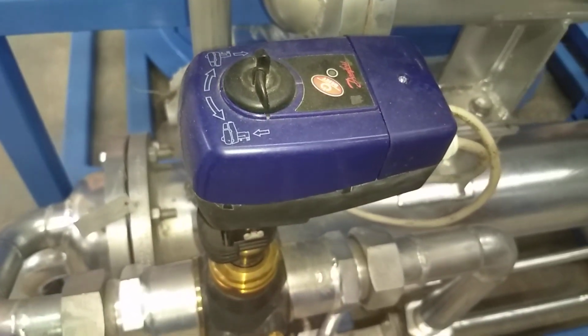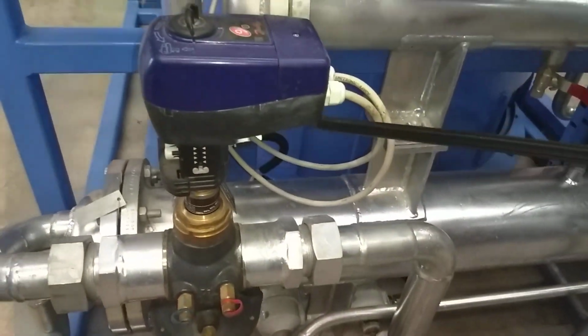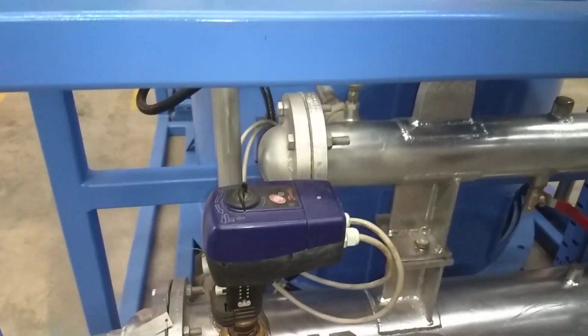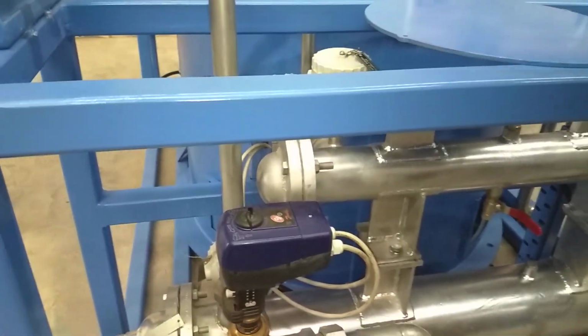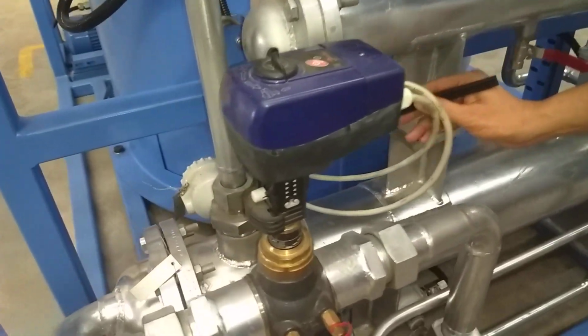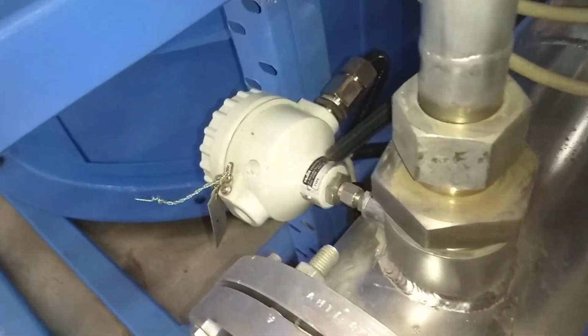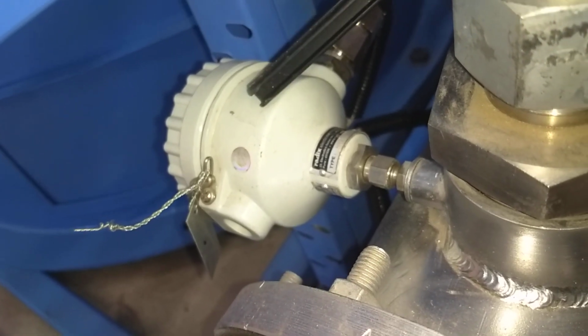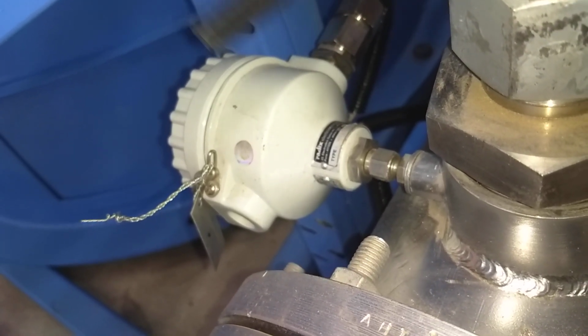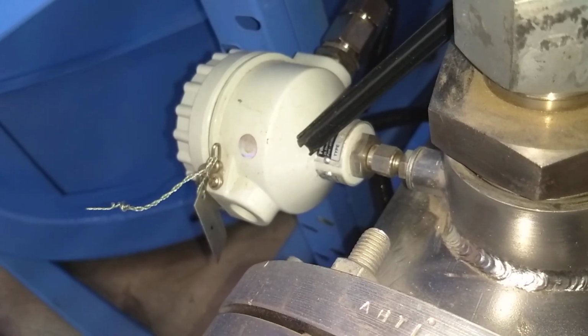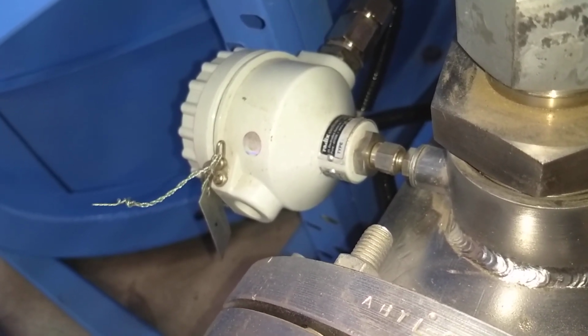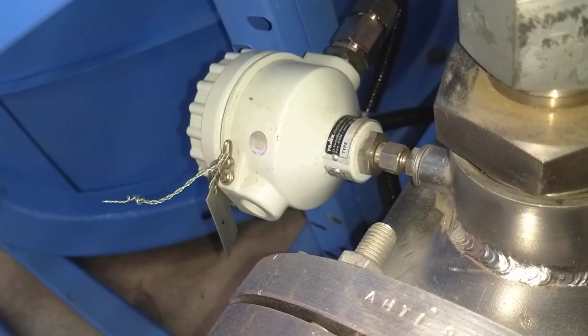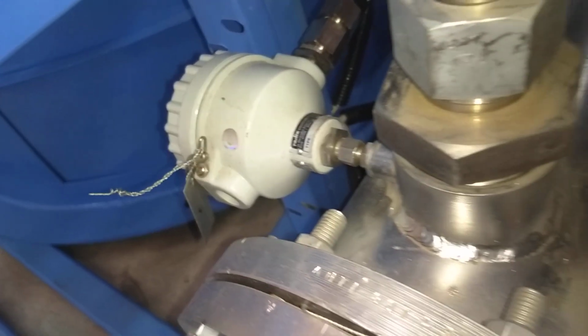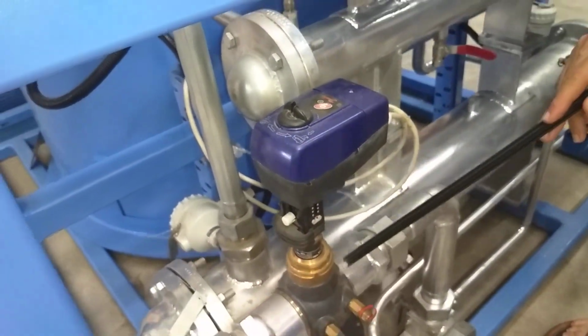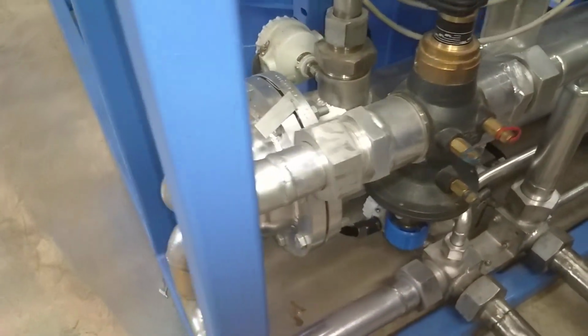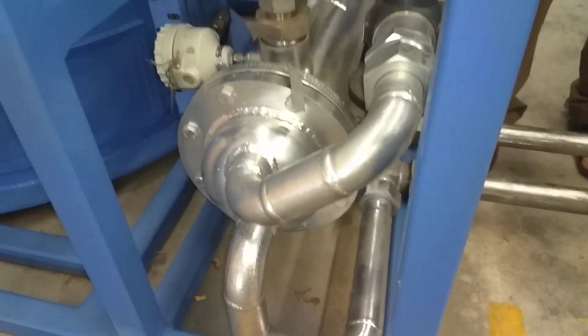This is the temperature control valve. This automatic valve maintains the temperature to the loco suction, and the feedback of that temperature is taken by this RTD sitting here. This is a temperature transmitter. This temperature transmitter gives the feedback to our PLC, and accordingly this PLC gives a control signal to our controller here, which controls the chilled water supply into the heat exchanger, and that is how the temperature of fuel here is being controlled.